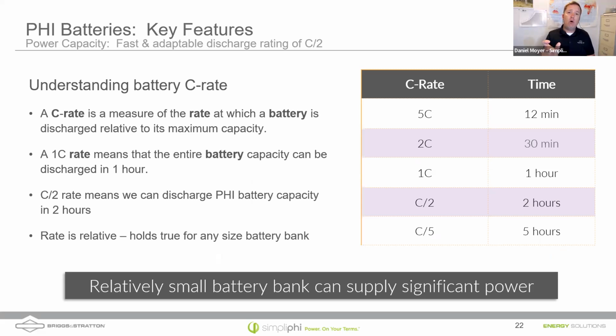That holds true for lithium-ion batteries in general when compared to lead-acid batteries. We have a C/2 charge rate, meaning you can charge or discharge one of our batteries in 2 hours. So if you have a generator running and want to charge up that battery bank quickly, you can run the generator at full tilt, get that battery charged up, and then shut it down.